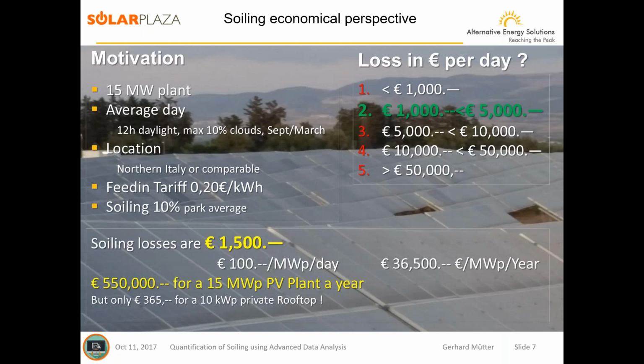Here's the result. The highest result we had was in the range from 1,000 to 5,000 euro a day on this 15 megawatt plant. That looks not very much, but it's nice to get this number, and I think it's not hard to keep: 10% soiling means 100 euro per megawatt peak and day that you're losing. 100 euro per day isn't much, but over the whole year it's 36,000 euro. If you have 2 megawatts, you can earn a second technician. If you have a 15 megawatt plant, it's twice as nice, because then you also get a manager and his car.